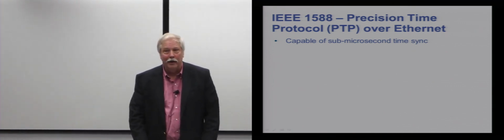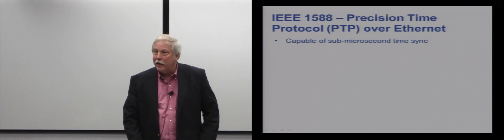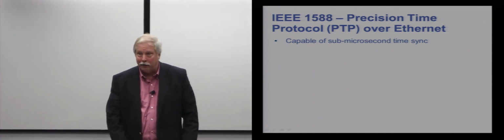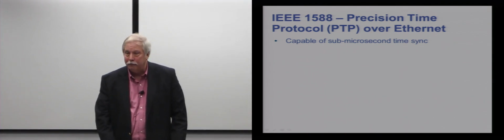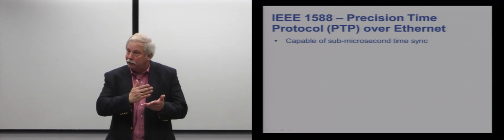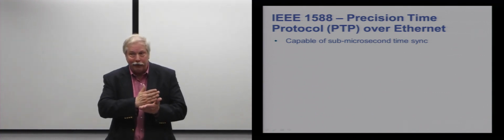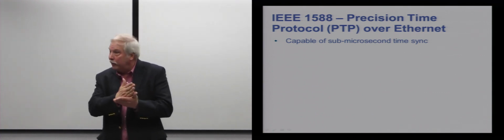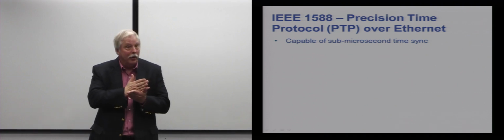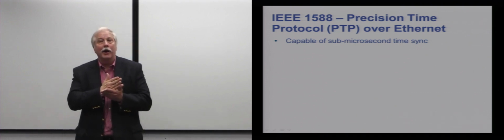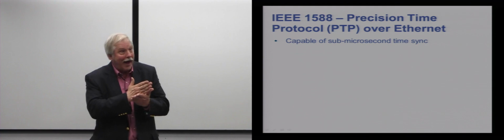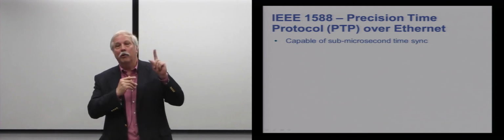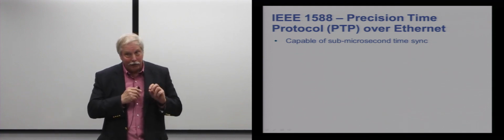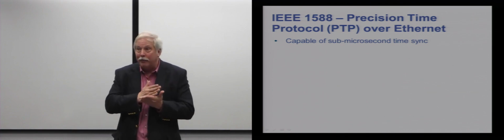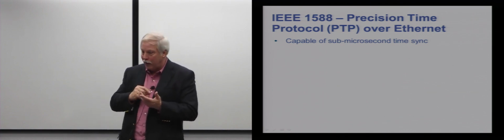PTP does that. There are now special Ethernet chips available in the products that protect and control the power system, so that when a message is sent from the device, the Ethernet chip puts a timestamp in the message, plus or minus 1 nanosecond of resolution. I'll use the right word: resolution, not necessarily accuracy, but it resolves the timestamp to the nearest 1 nanosecond.